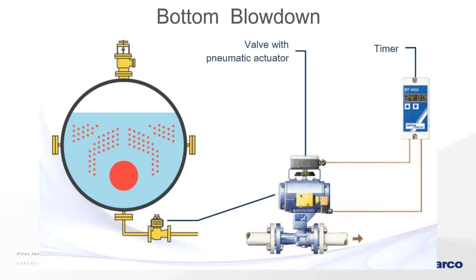So you can also have actuated blowdown. It could be set to a timer where you're blowing down, say, once every few hours or so for a set period of time. It ensures that it's more accurate, because even the best operator in the world, unless he's physically timing it, there will be a delay in the amount of time he's blowing down and the turning off of that valve. So an electrical or pneumatic means of doing that is more accurate. It means that when you put in, say, a 30-second blowdown, it is for 30 seconds. It's not for 32 or 28. So the argument is that it's more efficient because it's more reliable, and therefore less waste.